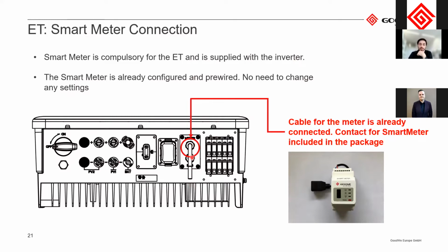And this is the connection to the meter, and this is a pre-wired RJ45 contact. I will show that later, and then either you use the cable supplied, or you can cut it and then use another connector if the cable is too long. The smart meter is also supplied in the package, and it's already pre-wired with 2 pins that go to the inverter, and then there is a connection socket for the RJ45 connection.